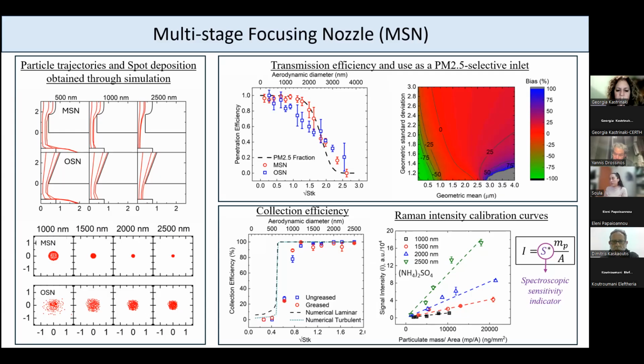Here, because I was able to control the different sizes that I wanted to get, I was able to get different calibration curves for different sizes. But when you have an aerosol sample outside in the ambient air, you might have some differences from your calibration curve, especially if you have a different peak size. This is something that you cannot avoid, unfortunately. I'm not sure if there are ways. This was something that my previous team was working on. They wanted to find ways to maybe apply some correction factors for that.